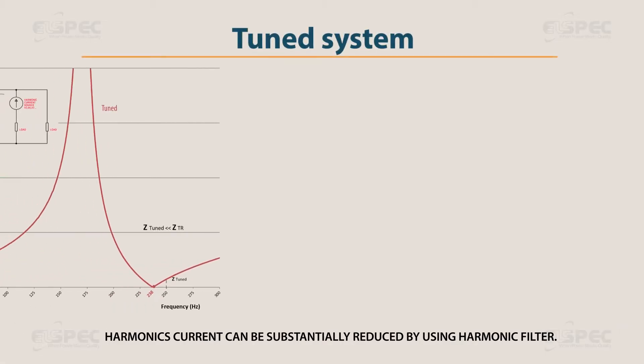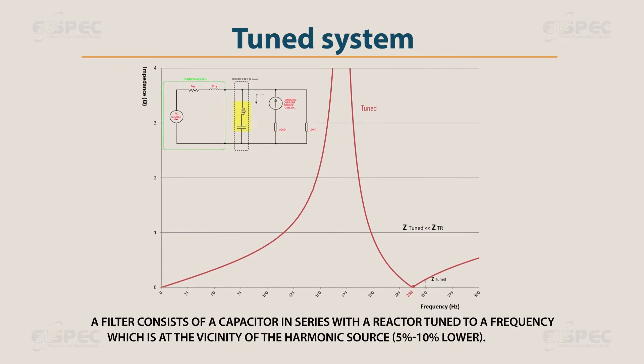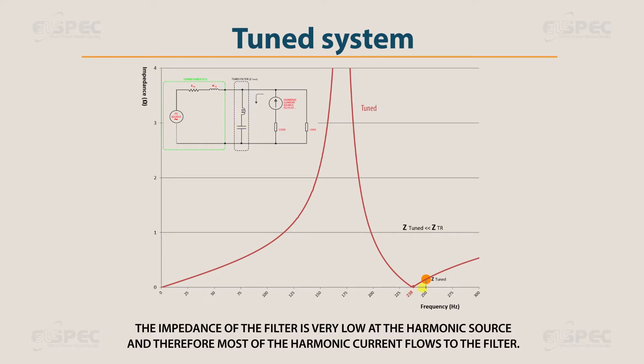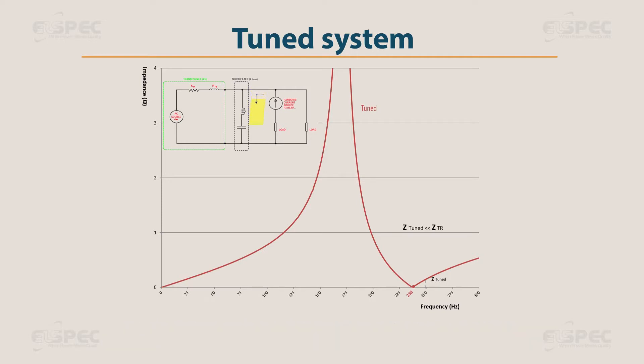Harmonic current can be substantially reduced by using a harmonic filter. A filter consists of a capacitor in series with a reactor, tuned to a frequency at the vicinity of the harmonic source — 5% to 10% lower. The impedance of the filter is very low at the harmonic source, and therefore most of the harmonic current flows to the filter. This way, the harmonic current doesn't flow toward the power source (transformer), and as a result, the voltage is not distorted.